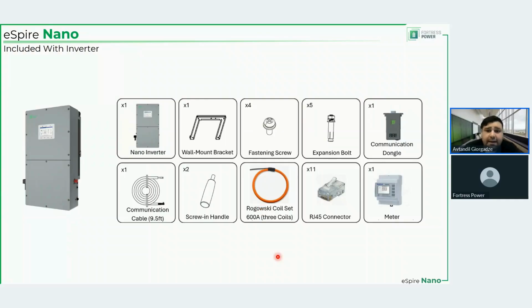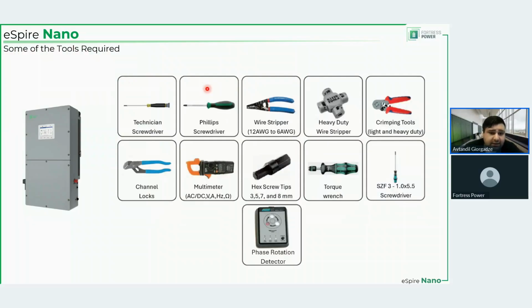of the inverter. Common tools that you're going to need, nothing too surprising, except for people that have not worked extensively in the commercial field. A phase rotation detector would be kind of the odd one here. It would be the odd one because on the residential side, you usually work with 240 volt split phase, which is a single phase split into 2 by the neutral, while here you have 3 lines, right? Which means you have 3 phases. The phase rotation must be clockwise, and you need to verify that with a phase rotation detector, because if the phase rotation is incorrect, that may result in imminent damage to the inverter.